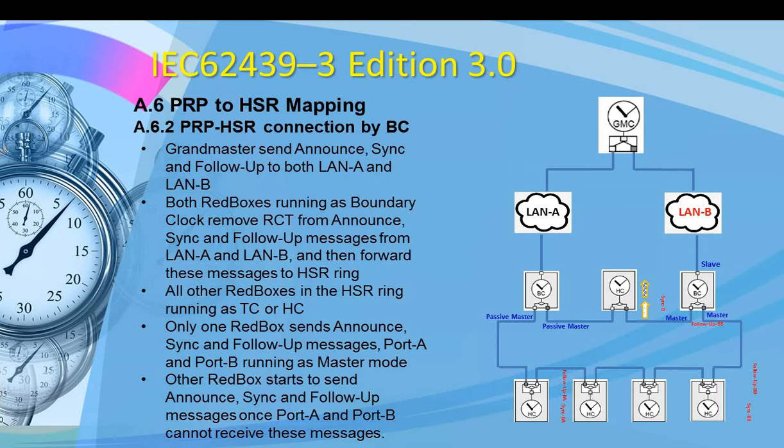We just highlight a few points here. The grandmaster sends announce, sync, and follow-up on both LAN A and LAN B. Both RedBoxes, this one and this one, are running as boundary clocks. They remove the PRP trailer from the announce message, sync message, and follow-up message coming from the grandmaster side.